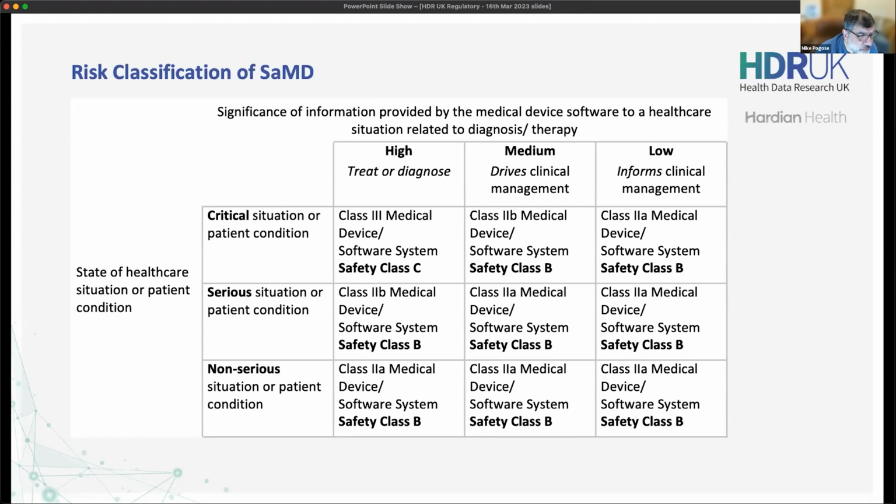Mixing hardware and software to achieve a functionality like the Apple Watch and its sensors. How do you draw the line between having purely software as a medical device, having hardware itself? Well, I think we started on that earlier. So thank you for that question. That's the start. If you have the sort of sensor that is on a consumer product, like the heart rate sensors on an Apple Watch, for instance, that's not a device because it's got its own purpose. It's only the software that adds to it to be a device.